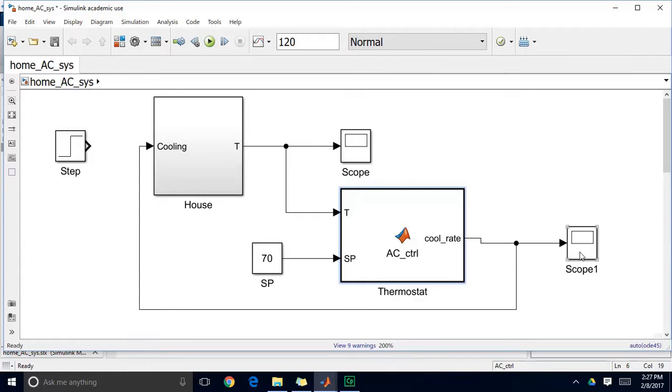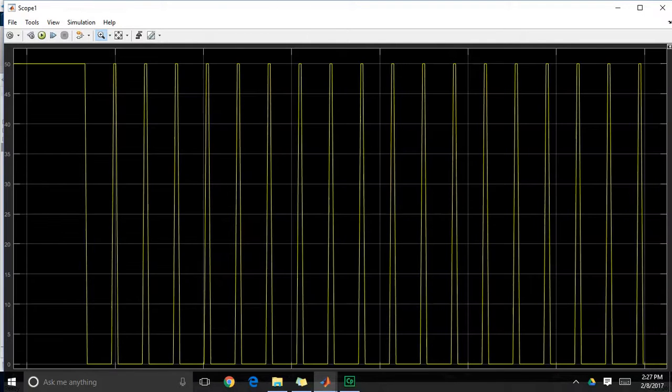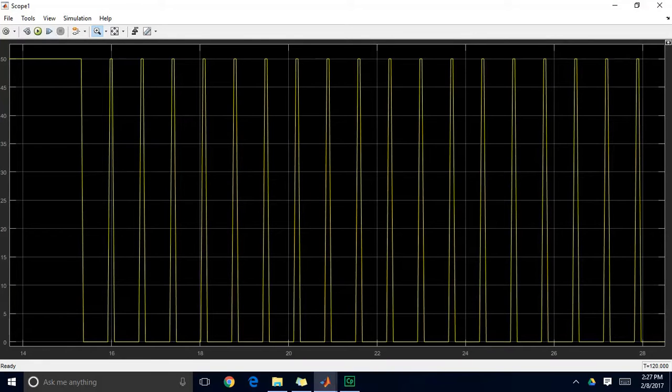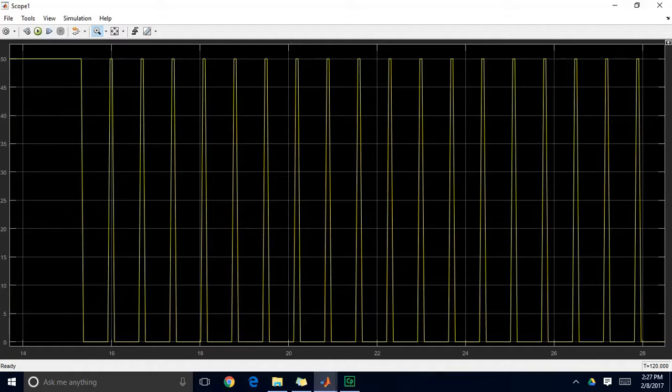So I'm going to look at my cooling rate first and as you can see I'm only simulating for 120 minutes but during that 120 minutes I'm doing dozens of switching events. So it's initially on until I get below my set point then it turns off then it has to turn back on. If I zoom in to get a higher resolution on my time you can see that within a period of just a few minutes, here's two minutes, we're switching the system on three almost four different times. So there's this very frequent switching.